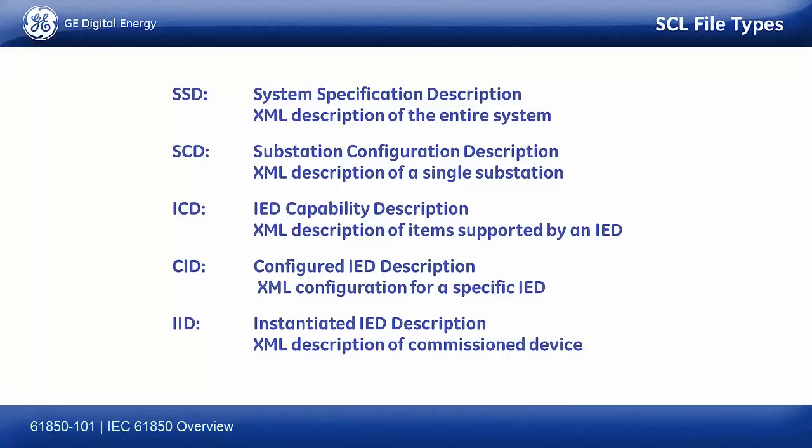And then the second version of part six of the standard talks about an IID file, which is an instantiated IED description. It's an ICD file that's been instantiated. It defines the device in some specific configuration for a specific version of the device, right?